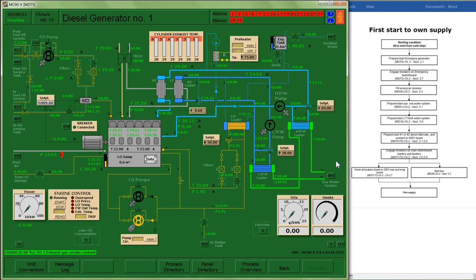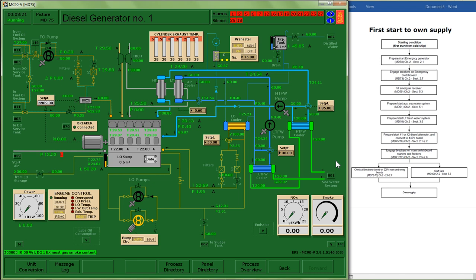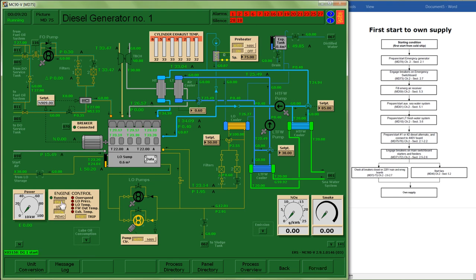When I do have my generator finally started, I will be connecting it electrically, so my diesel generator will run. I will turn on its voltage control, and we will complete our pathway so that it ultimately is supplying my emergency bus. I can see I've got over 15 bar now. I'm in local mode, no trips showing, and I will start my generator.